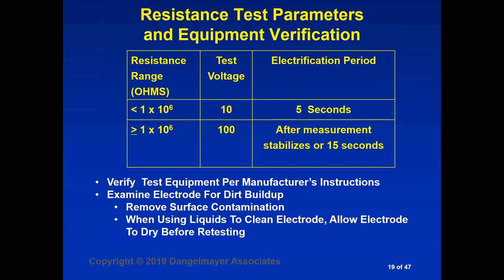So you want to verify your test equipment first, before you go out to make these resistance measurements. You want to look at the electrode, make sure that it's not dirty. You want to remove surface contamination from that electrode. I'll show you a picture of the electrode in a minute. And when using liquids to clean the electrode, you need to allow it to dry before you start retesting using the electrode you've just cleaned.